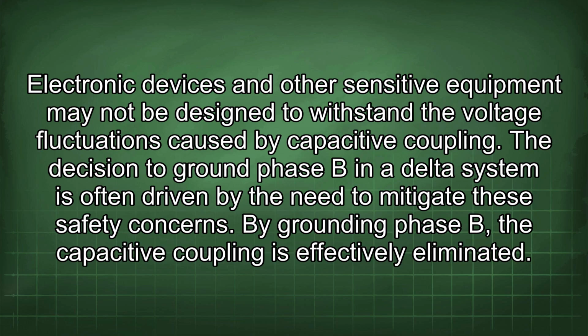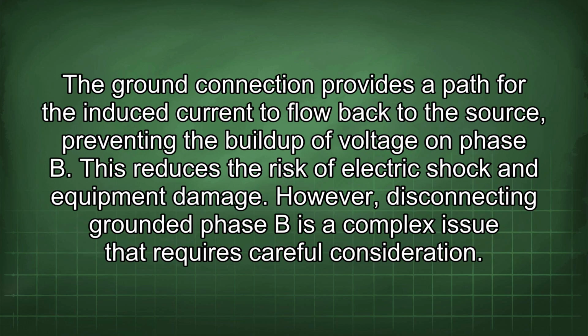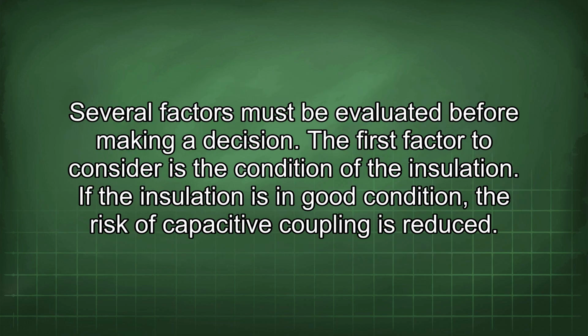The decision to ground phase B in a delta system is often driven by the need to mitigate these safety concerns. By grounding phase B, the capacitive coupling is effectively eliminated. The ground connection provides a path for the induced current to flow back to the source, preventing the buildup of voltage on phase B. This reduces the risk of electric shock and equipment damage. However, disconnecting grounded phase B is a complex issue that requires careful consideration. Several factors must be evaluated before making a decision.